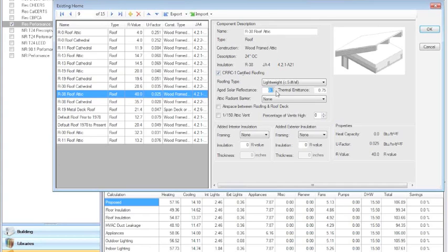And so we could come along and say, okay, we're going to upgrade this and we're going to put a tile roof up there. And a tile roof is going to have a solar reflectance of 44%. And we'll leave thermal emittance at 75%. Now, where did I get 44% from? I went to coolroofs.org. That's their website, www.coolroofs.org, and I looked up the performance of that particular roof. Okay, so there's one example of how we can do a more sophisticated modeling of the roof situation.